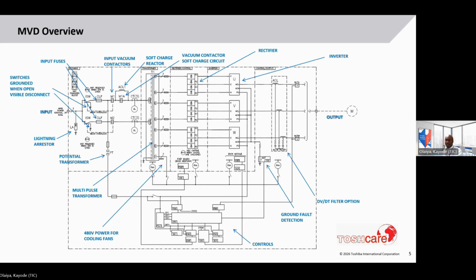There is a single line diagram here showing the components in the Toshiba medium voltage drive. Starting from the input, we have lightning arresters, which protect against shocks to the input voltage. We have an isolation switch, which is the main point of isolation for the drive, and it grounds when open.